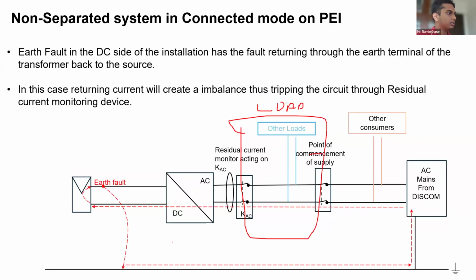So in these cases, if there is any earth fault, if the discom is still operating, I mean, if the transformer is still in a good condition, and if the system referencing conductor is still in a good condition, it will go back to the source, and the residual current monitoring device will act on the protective device. But the problem is, if this supply is not there, if it is an islanding PEI, islanding prosumer installation, and something happens to this system referencing conductor, that is where the problem starts.